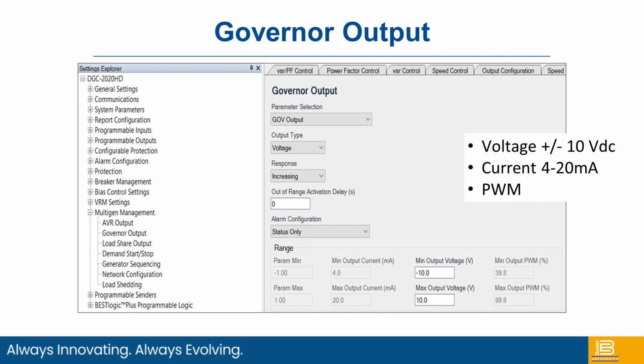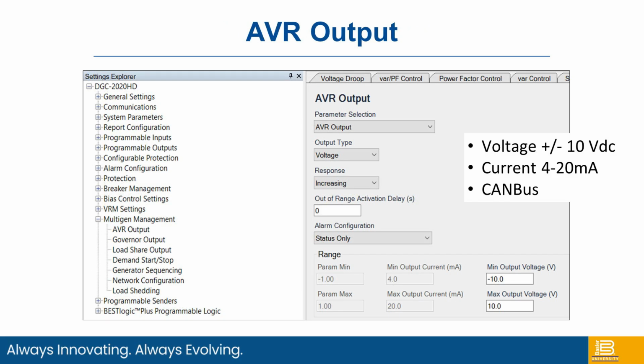Some of the adjustments for the governor. If it's an external analog style governor, we can control it with voltage to plus or minus 10 volts, current of 4 to 20 milliamps, or pulse width modulation. If it's an ECU, then there's a drop down within the governor settings where you can select the governor and the ECU that you have. And again, just like the AVRs, there are multiple drop downs that we already have pre-configured. AVR output is similar. If it's an external analog bias to the voltage regulator, we have the same plus or minus 10 volts DC, 4 to 20 milliamps, or we can communicate over the CAN bus.